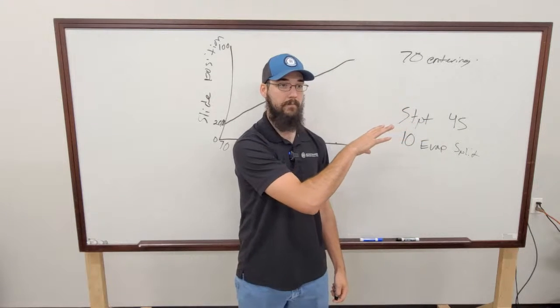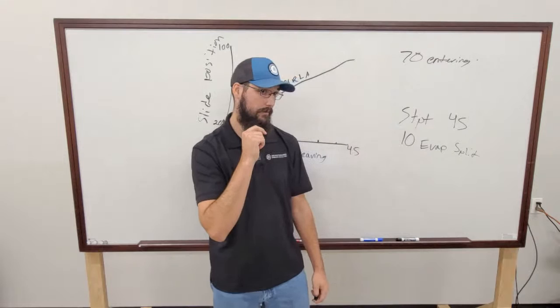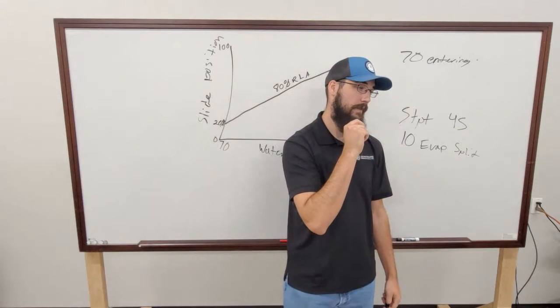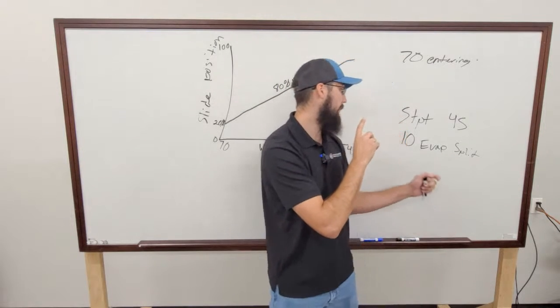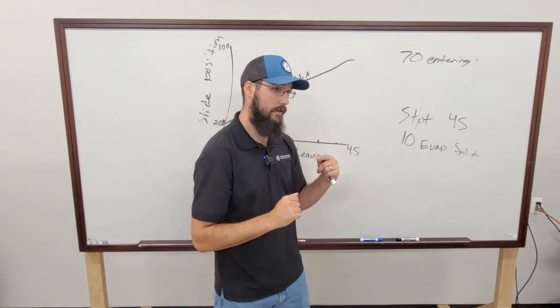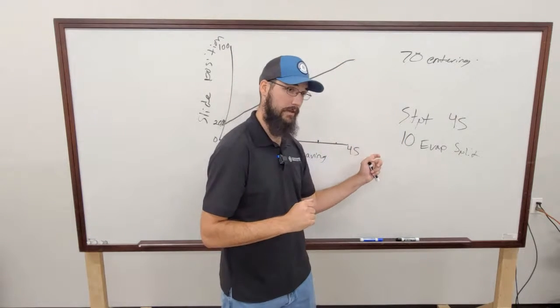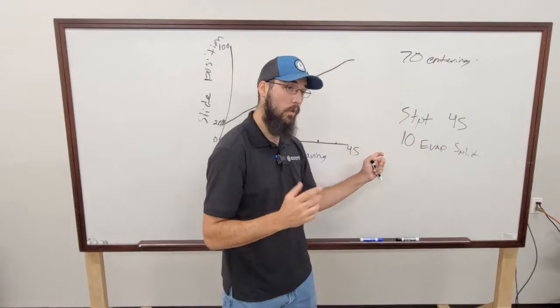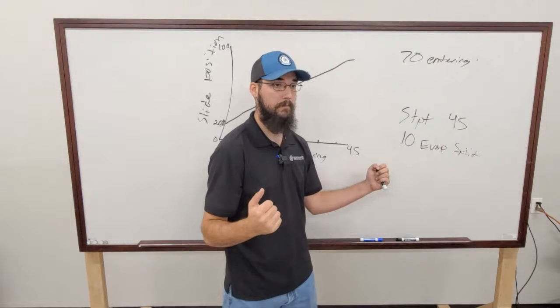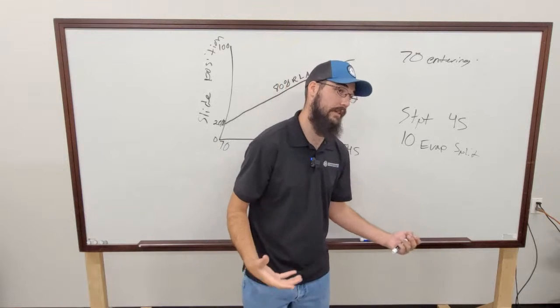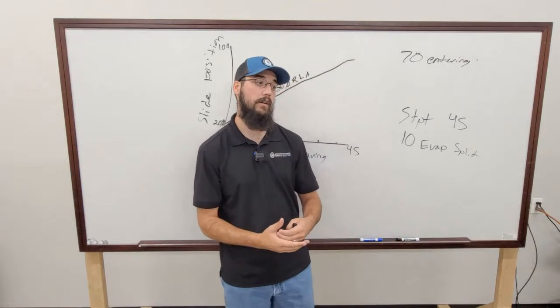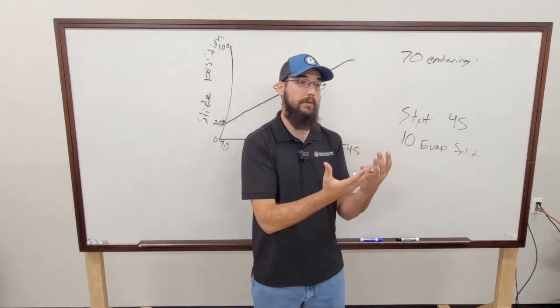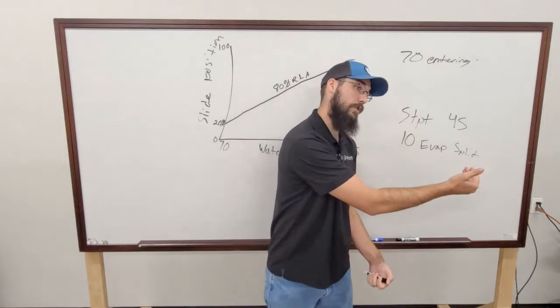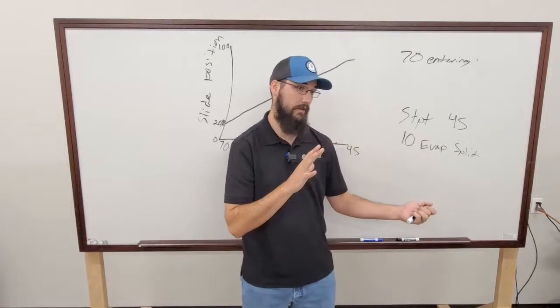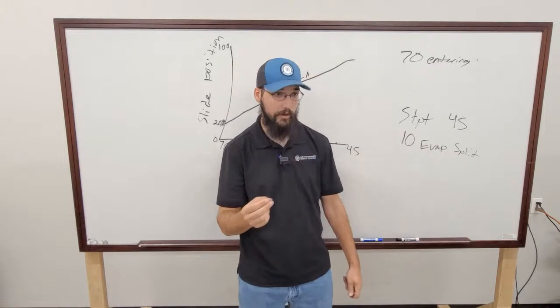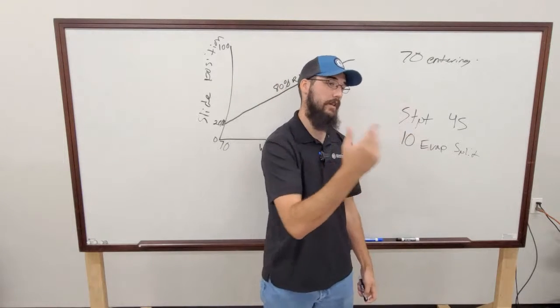And that's based on your split? What is? Your water, your inlet and outlet water? It could be, more specifically, not inlet outlet. It would be deviation from set point. Gotcha. Well, yeah. Or time. So if the machine was completely off and it goes into a startup, it can either go into a pull down regardless of deviation or deviation itself. Gotcha.